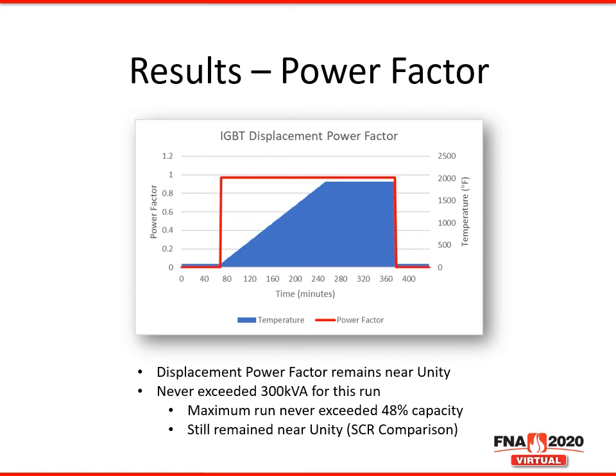One thing I want to point out here is that we matched our system to the 645 kVA VRT. During this cycle, the IGBT MFDC system never exceeded 300 kVA. So, at its maximum operating point, it was still 48% of the total capacity. It was even lower than that during most of the cycle. The take-home point is that the IGBT MFDC power supply has a very good displacement power factor at any practical set point.